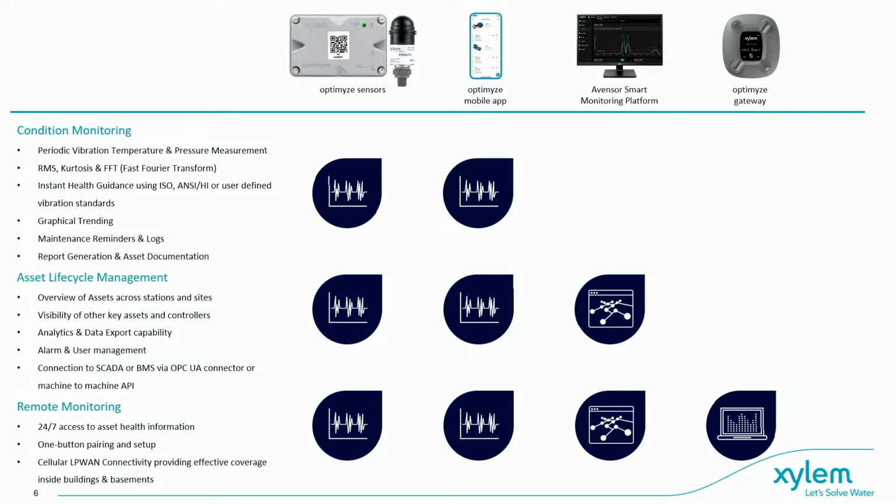Okay, we do have a question. What is the reading frequency window for the pressure sensor and also the vibration sensor? Like the range? I'm assuming they're talking about the Bluetooth range? Or what is the reading frequency? The reading frequency window is the question. So I think it's how often the readings are being taken? Yeah, so that's programmable. I believe it's preset in the application as every 15 minutes. However, you can tell it to take readings every 5 seconds to every 24 plus hours. So that is all based on whatever your preference is there.